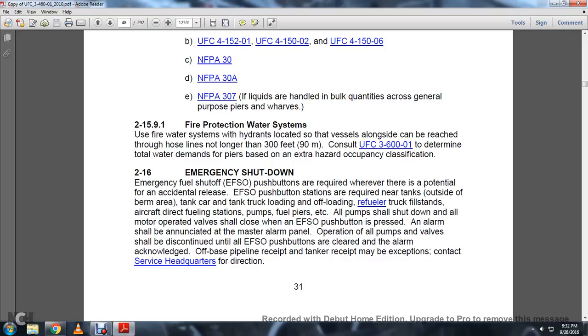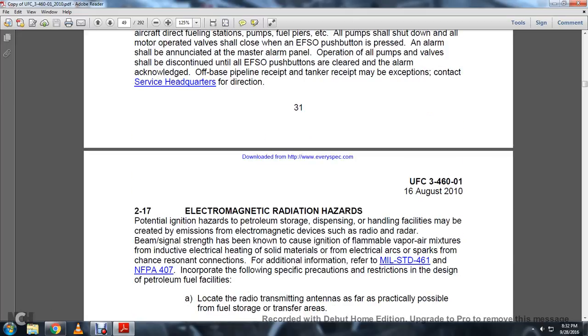When the emergency fuel shutoff button is pressed, an alarm shall be initiated at the master alarm panel. All pumps and valves shall be discontinued until the emergency fuel shutoff push buttons are cleared with the alarm acknowledgement. Offshore pipeline basis receipt of the tanker's receipt with may exemptions. Contact the service headquarters for direction.